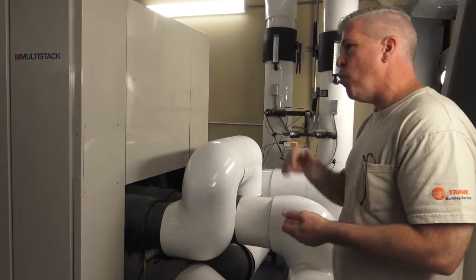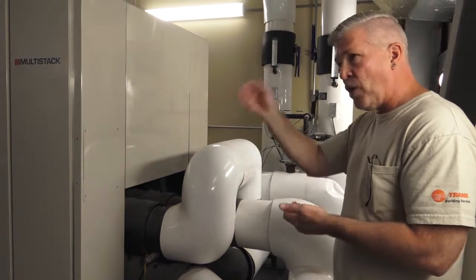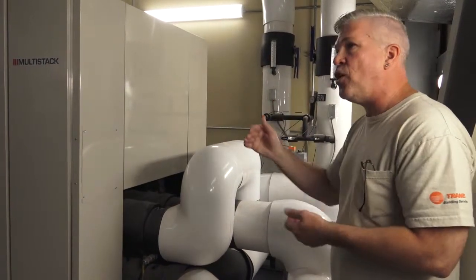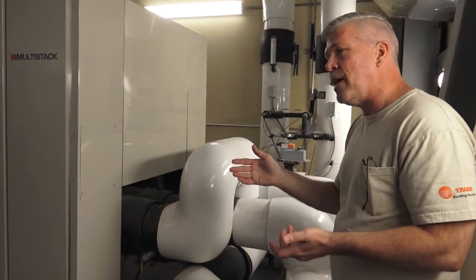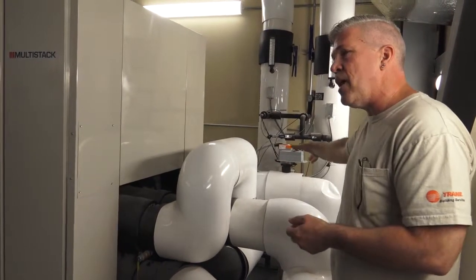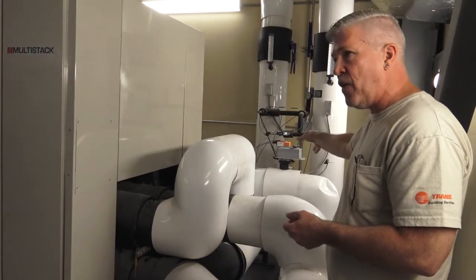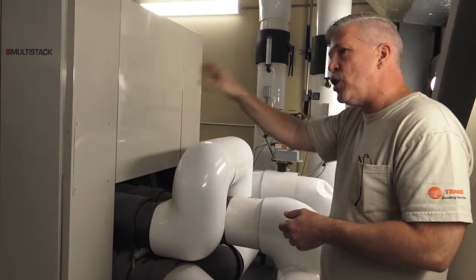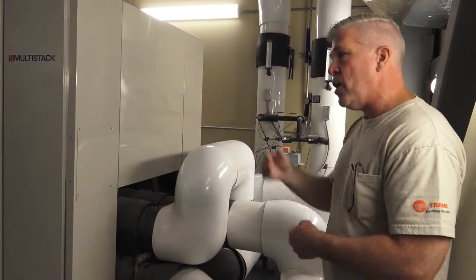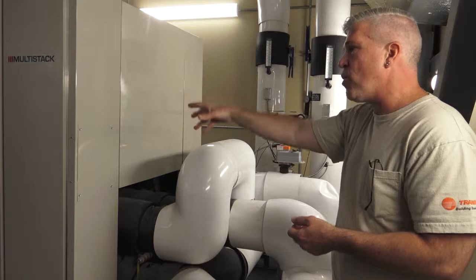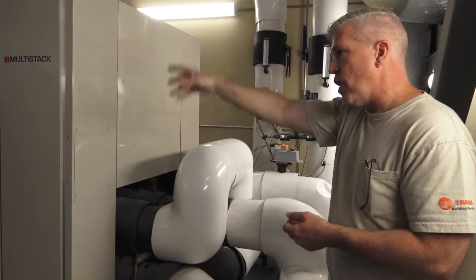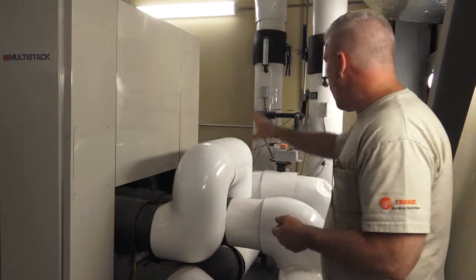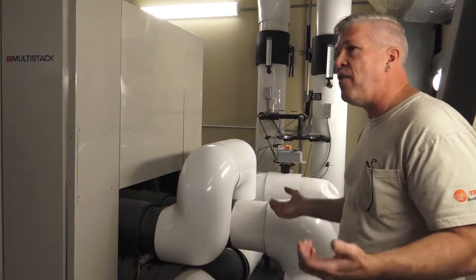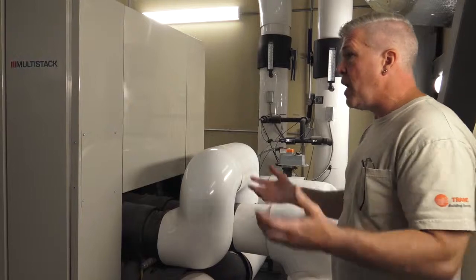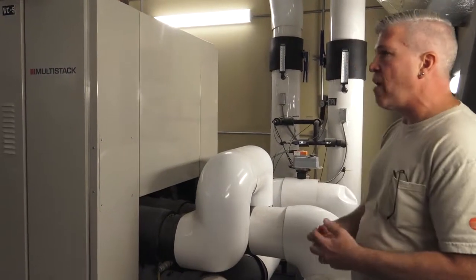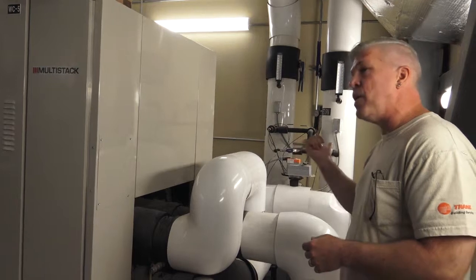So during the summer, it wouldn't be surprising to see the geofield with a really high flow, and the water temperature could be like 100 degrees or something like that. And you may be going, what's that all about? But it's the excessive hot water that this is producing that it's dumping out to the field, while it's trying to create the chill water that it needs. And then during the winter, you'd see just the opposite. You might be creating your 120, but by doing that, you're creating an excess of chilled water. So you might see water leaving to the geofield that's at like 35 degrees. And it could be at a high flow rate, which is really deceiving, because you can have like 1 million BTUs of chill water dumping down to your field.